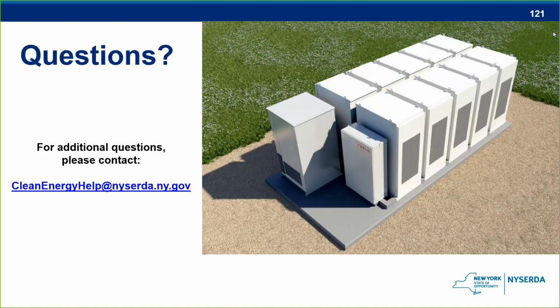Okay. Yeah, this is Jen. I can reiterate a little bit of what I touched on. I'm not as familiar with the New York City specific fire code, more so the state fire code. But, and it was on one of the previous slides, I forget which number, the outdoor walk-in units are treated as outdoor systems, so they have slightly fewer requirements than an indoor system would, provided that those walk-in units are below that volume threshold, which is approximately the size of a shipping container. If it's any bigger than that, then it is actually treated as an indoor system, like it's a building.